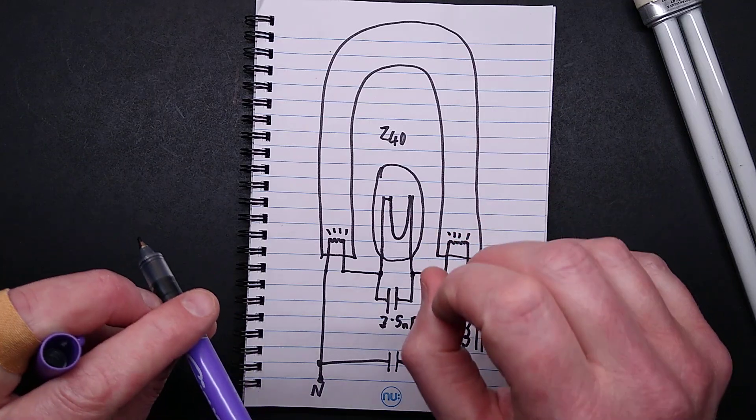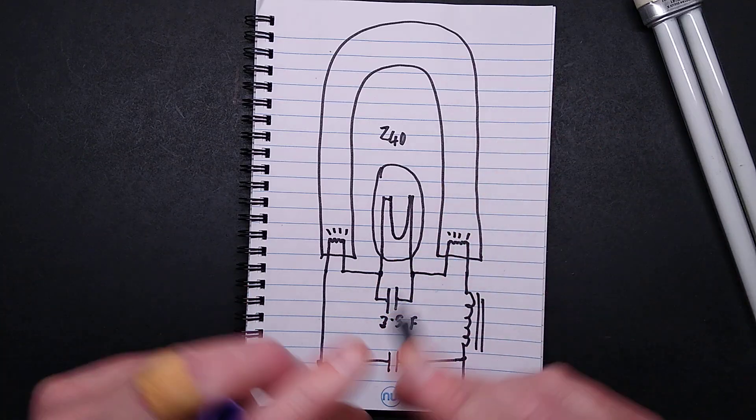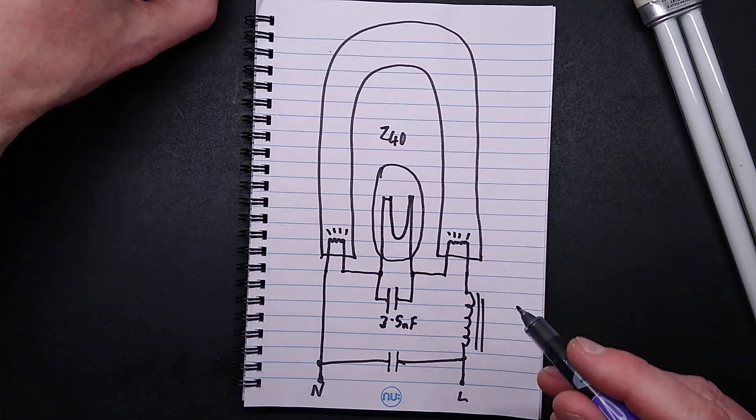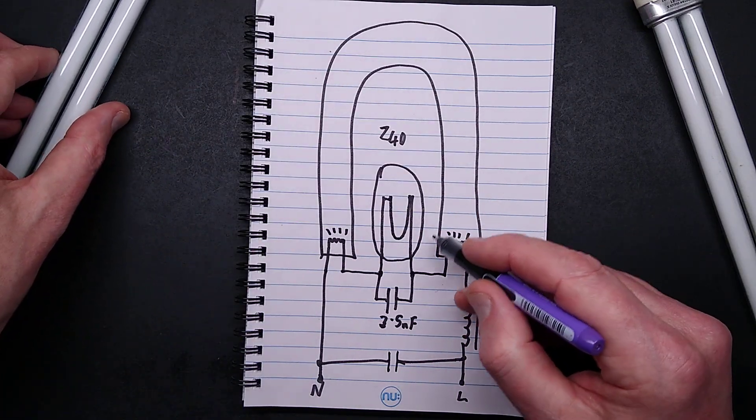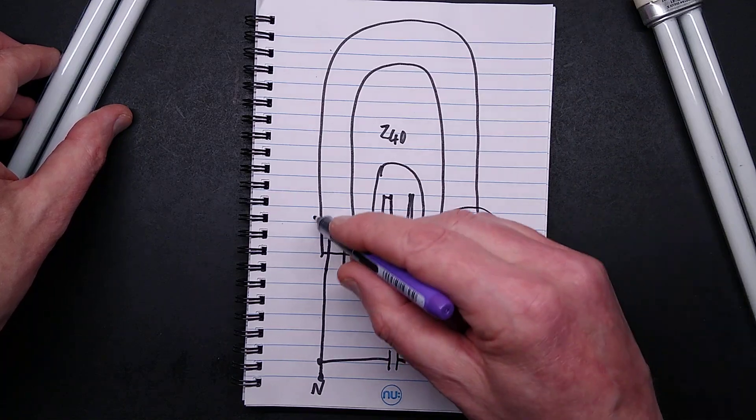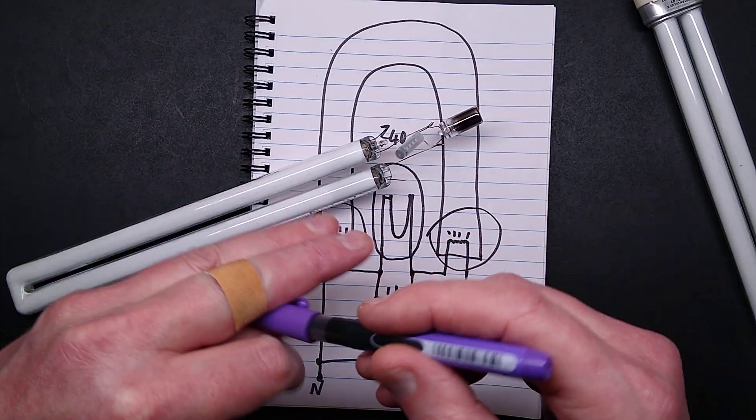The other thing you'll often see, particularly with tubes like this, is it just glowing orange at the end. If it's basically just glowing orange around the end here, there's a good chance the starter has welded.